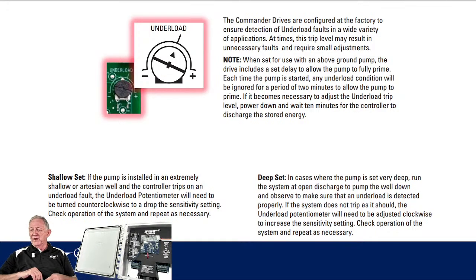Now, I think this is coming down to one of the last slides. They're on your screen right now. But when we look at those occasions where we need to make tweaks to that underload, these are some of those occasions that may occur, all right? And again, everything that we're seeing here is in the instruction manual. If you look down at the bottom right, it says shallow set: if the pump is installed in an extremely shallow or an artesian well, where you've got water coming right up over the top, and the controller trips on an underload fault, the underload potentiometer will need to be turned counterclockwise to drop that sensitivity setting back. We'll just repeat it as necessary to get rid of that nuisance trip.